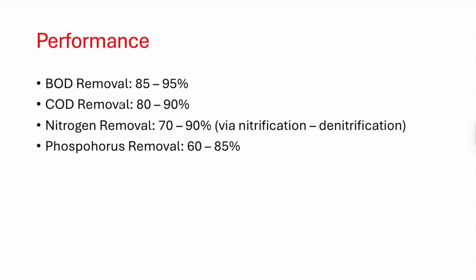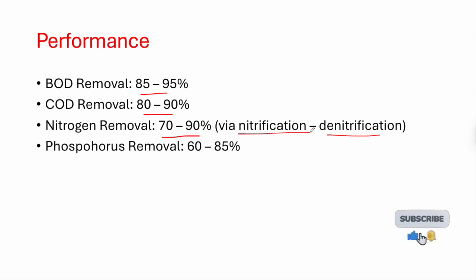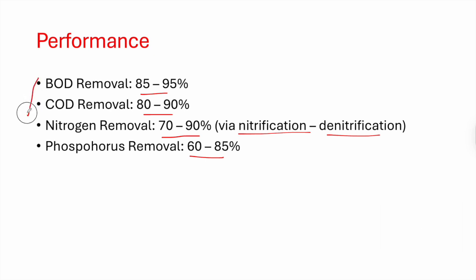Regarding performance, the SBR delivers BOD removal of 85–95%, COD reduction of 80–90%, nitrogen removal of 70–90% when proper denitrification during filling and nitrification during aeration are applied, and phosphorus removal of 60–85%. These are strong numbers, and the SBR is a very effective method when well designed.